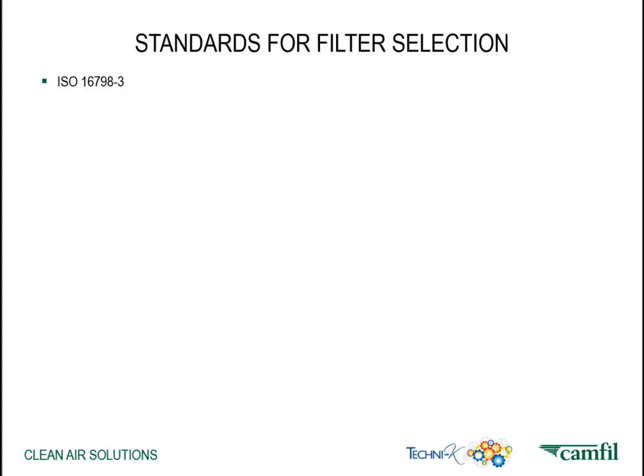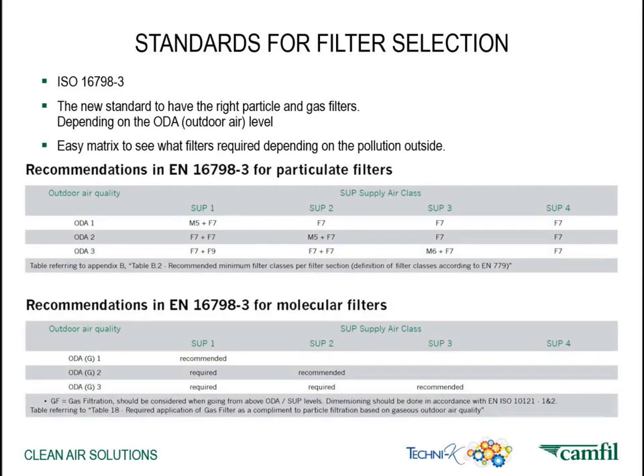So how to choose filters according to the new standard? The new standard ISO 16798-3 sets the need for filters according to the outdoor pollutants. It's the new standard to have the right particle and gas filters in air handling units, depending on the outdoor air pollution. Use the standard matrix to see what filters are required depending on the pollution outside. In the matrix, we have different types of outdoor air quality and different supply air filtration recommendations depending on the desired indoor air quality. This shows both particle and molecular filter needs. If you are in any doubt, please contact your local Camfil representative and they can evaluate this for you.